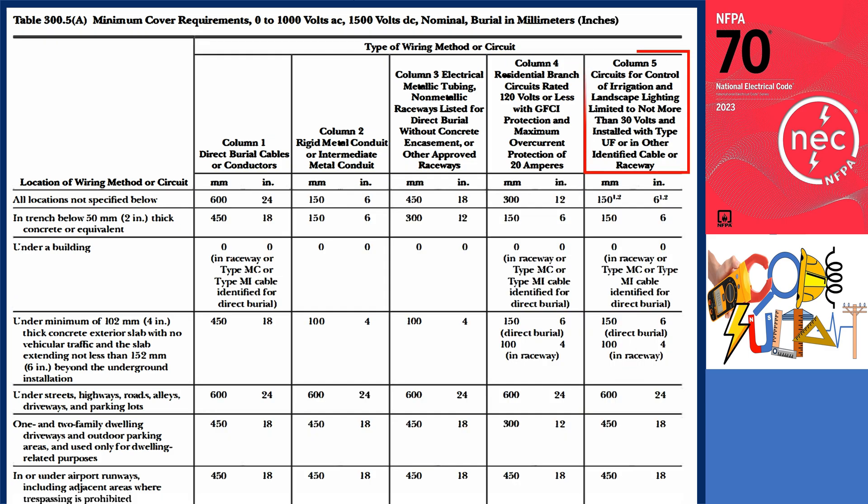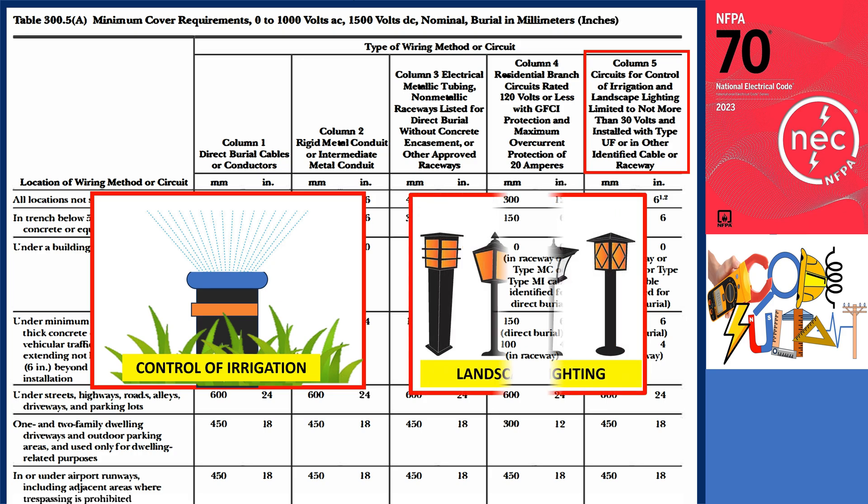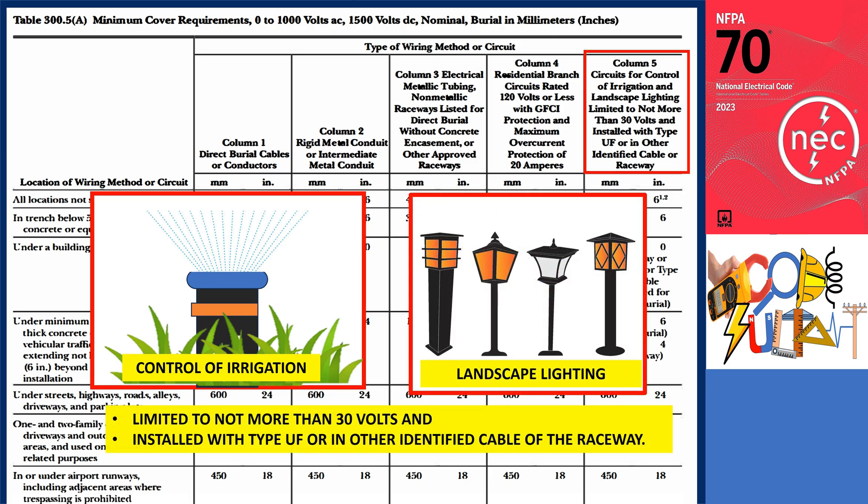Column 5 covers circuits for irrigation and landscape lighting, limited to not more than 30 volts and installed with type UF or other identified cable or raceway.